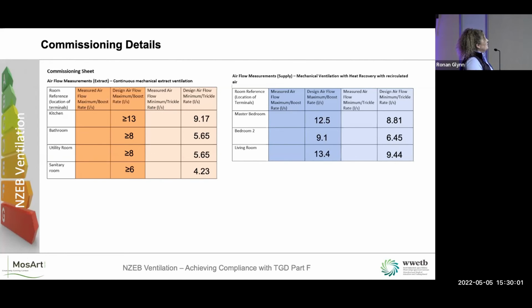The measured airflow rate on site then is what the commissioner does. So he measures it on site and he writes down the answer that he gets. The same for the boost, you calculate it and then you measure it on site. Same for the extract and the boost on extract. So these are all calculated and taken from Part F. They're table 1 for CMEV, table 2 for MVHR, but it's exactly the same information.